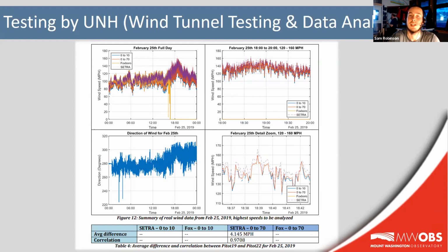70 sensor in pitot 19 and the 0 to 70 sensor in pitot 22 for the period of 6 p.m. to 8 p.m. Eastern Standard Time, where winds were in the range of 120 to 160 miles per hour. And if you notice, it's in 24-hour time there, so it's between the period of 1800 hours and 2000 hours. I did some investigating myself, and the average wind speed for this period of time was 136 miles an hour. So an average difference of 4.1 is only a 3% difference, which is well within those requirements set in place by the World Meteorological Organization.